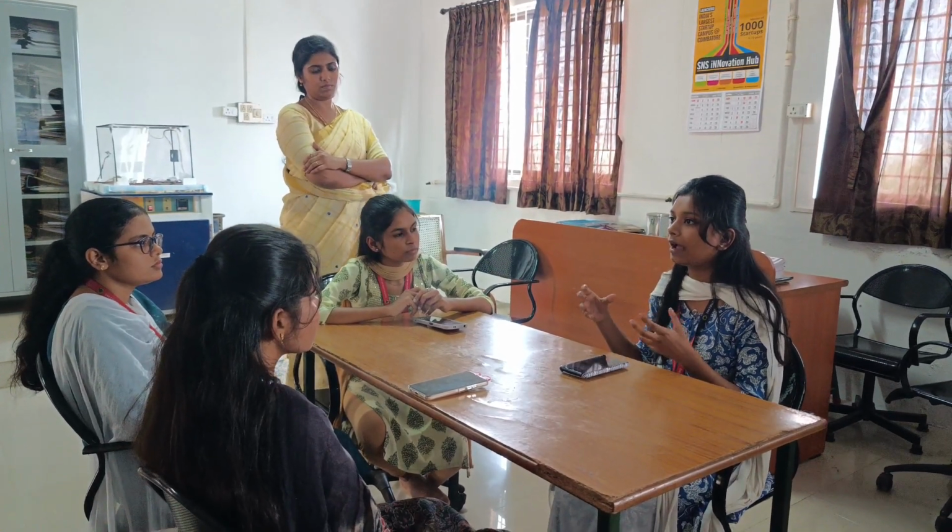And limiting the patients' direct contact with electrical appliances. For example, in biomedical instruments we use conductors and transducers directly on the body, such as defibrillators. We can arrange them in such a way that they do not affect the patient in any way. Also isolation transformers: we can't have a power supply in direct contact with the patient, so we can have an isolation transformer.